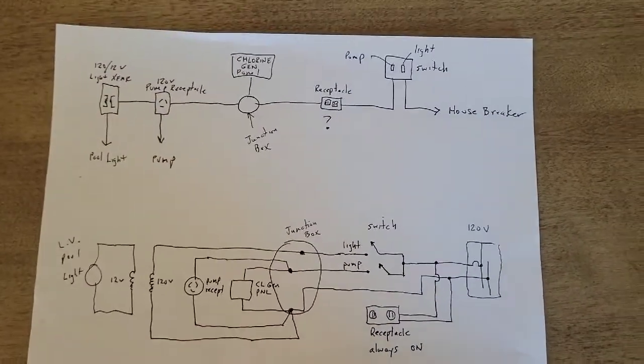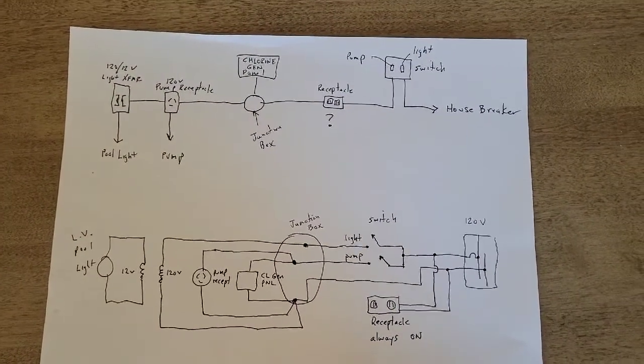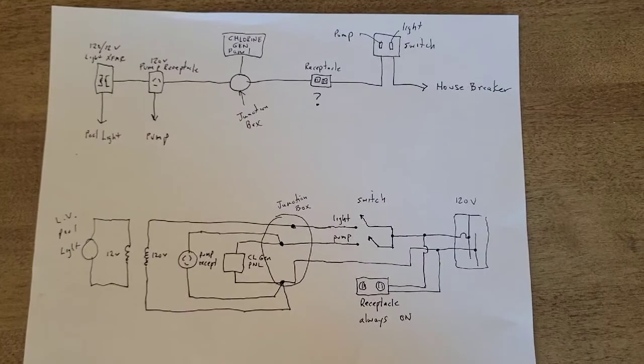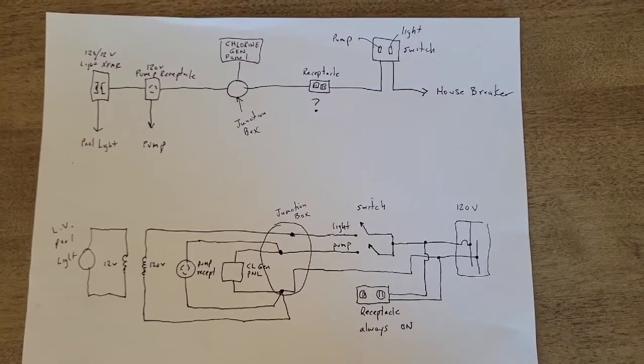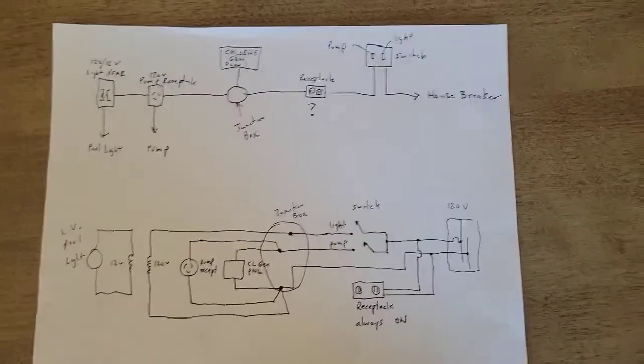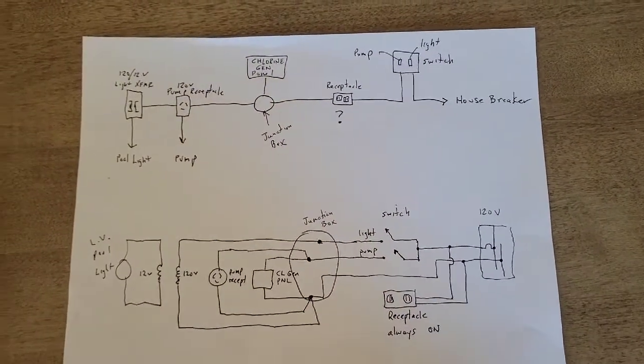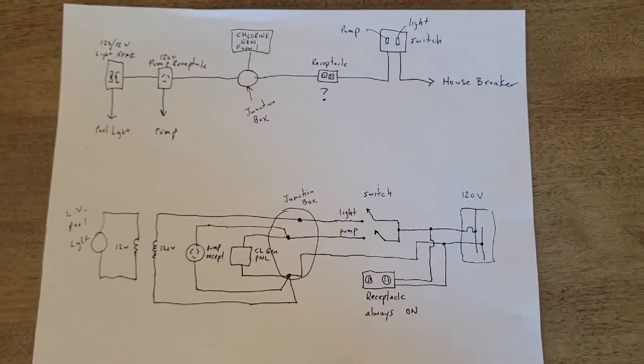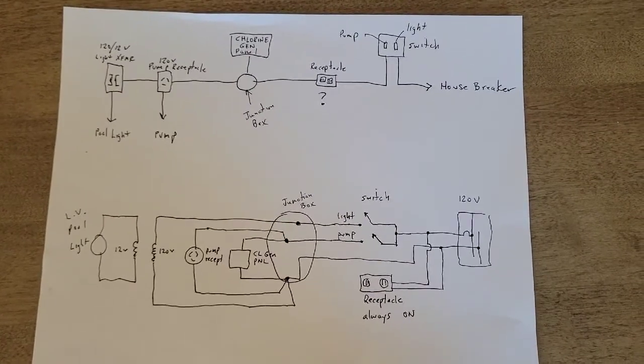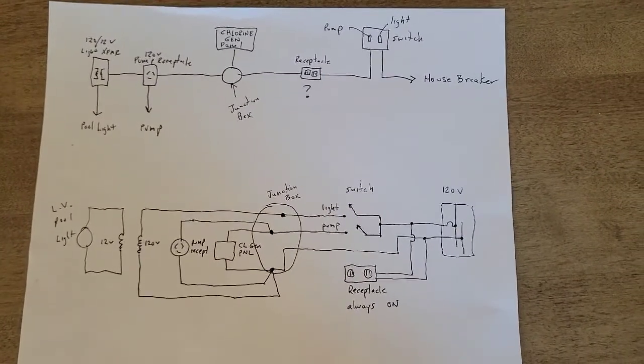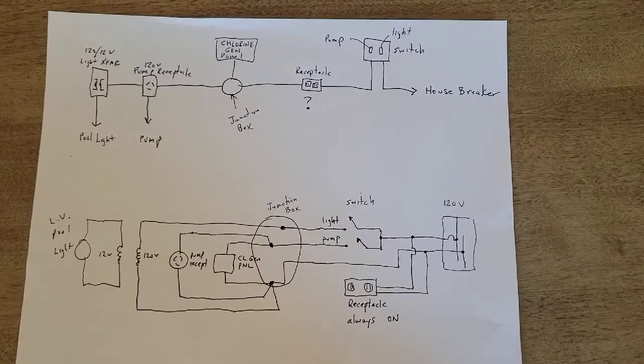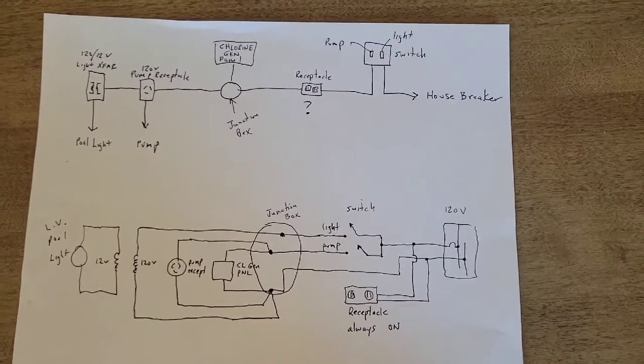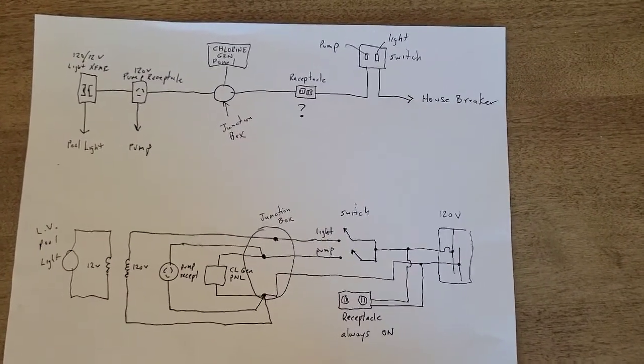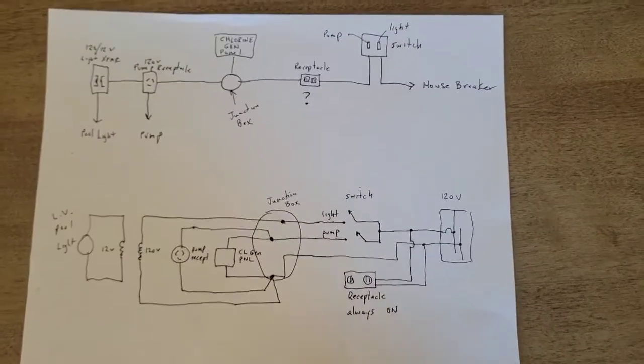So this is what the outside looks like, so we can continue troubleshooting a little more intelligently, electrically, what's going on. But I expected to come over and start tearing the switch apart and looking at what might be wrong. And he was mucking with the pump, and that was still leaking. And then he, of course, had the seal reversed. So he's putting that back together. We're going to go see if we fix the leak, get the pump working, and then revisit the source issue that I think is going on.